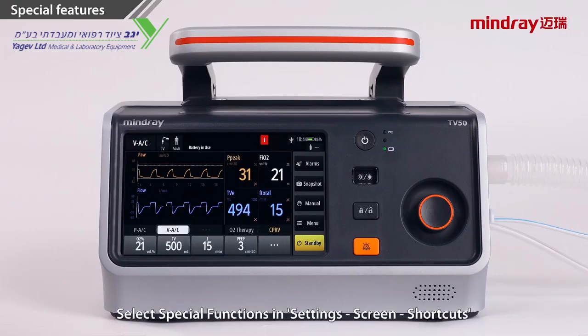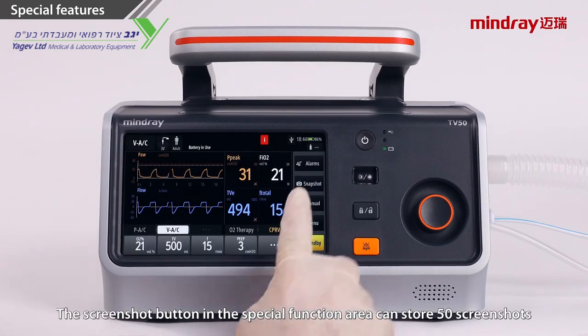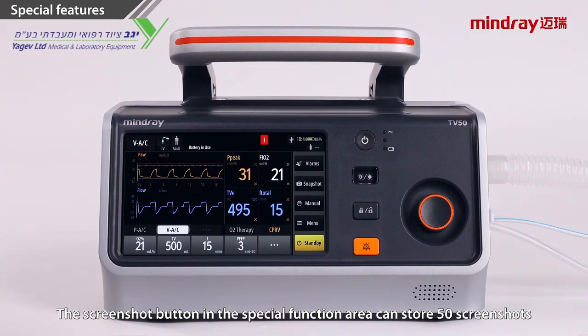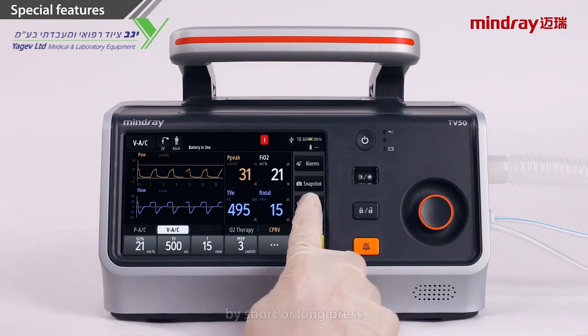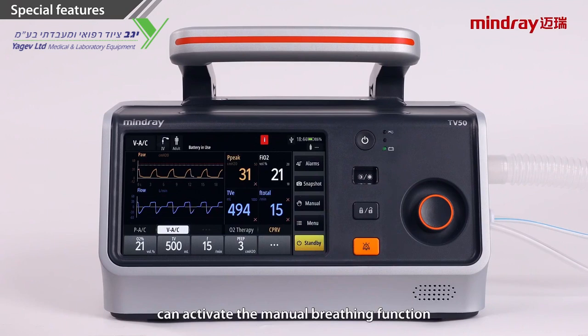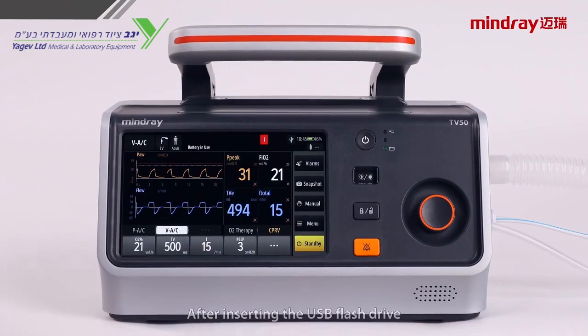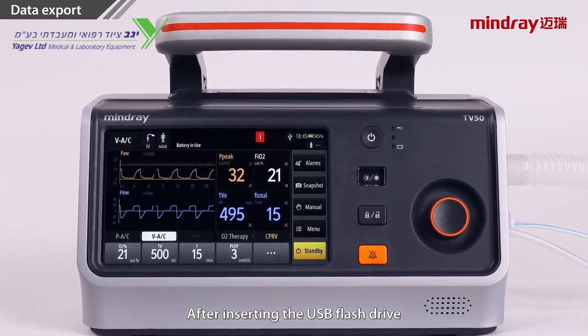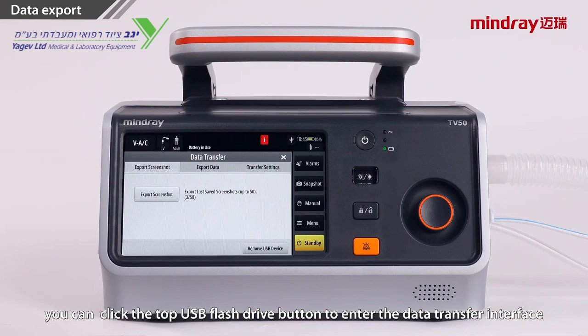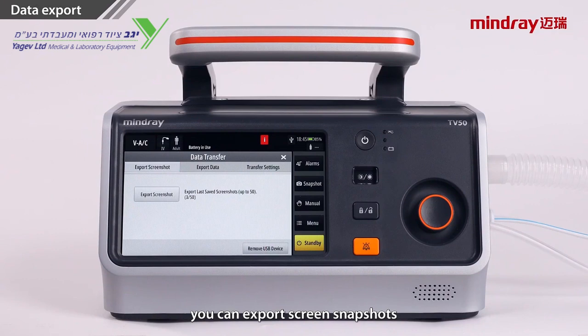Select Special Function in Settings, Screen, Shortcuts. The Screenshot button in the Special Function area can store 50 screenshots and the data can be exported via USB flash drive. The Manual button in the Special Function area, by short or long press, can activate the manual breathing function and inhalation hold function. After inserting the USB flash drive, you can click the top USB flash drive button to enter the data transfer interface. You can export screenshots, system logs, and transfer settings.